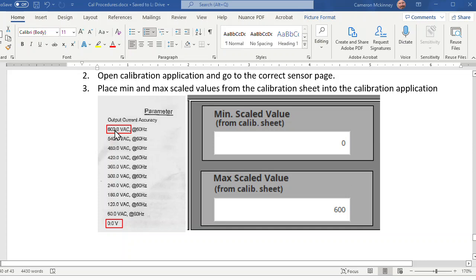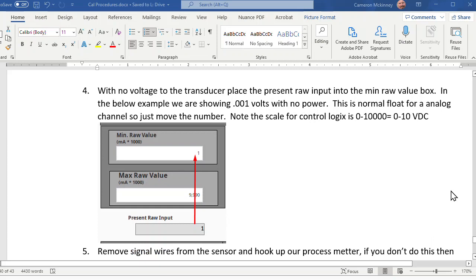So I've already done this. We've placed the min and max values from our calibration sheet in there. With no voltage to the transducer, place the raw present input value. It was floating at 0.001 volts, so it doesn't matter. We're just going to move that in there, because we don't care what that signal is if it's within reason. If it's 0.001 off, that's going to be our low. If I was showing like 1,000 there, then something's wrong with the card and it needs changed. So the scale for Control Logix is 0 to 10,000, and engineering units is 0 to 10 VDC.